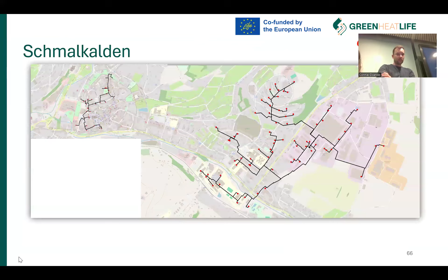Did I see correctly in one of the early slides the temperature—I think you mentioned the district heating system and the scenario of supply temperature reduction, showing two heating curves. Let me go back to the slides. Here you can see that in red we have the historic supply temperatures measured, and in dark blue or black we see the optimized supply temperatures. I think the question was that during higher outside temperatures we have higher optimized supply temperatures. Yes, this is correct, because the digital twin sees that the return temperatures from a historic point of view are quite high in that network.